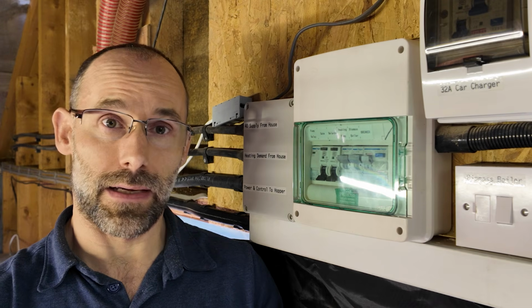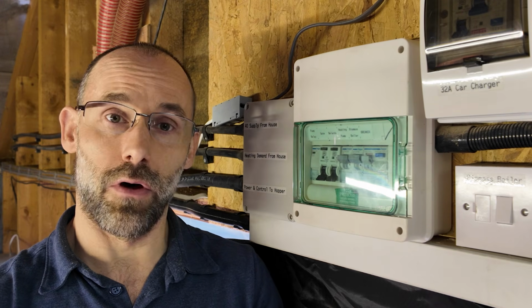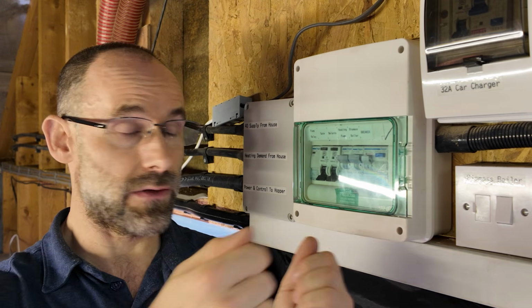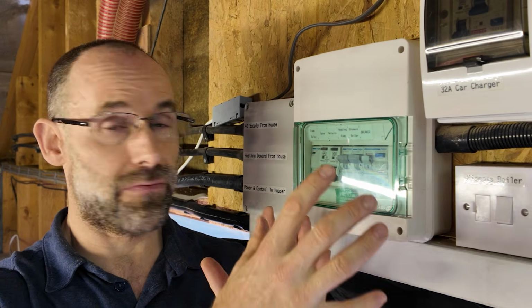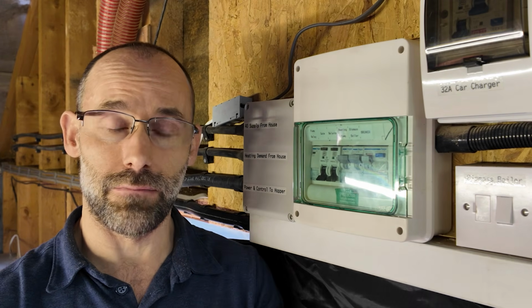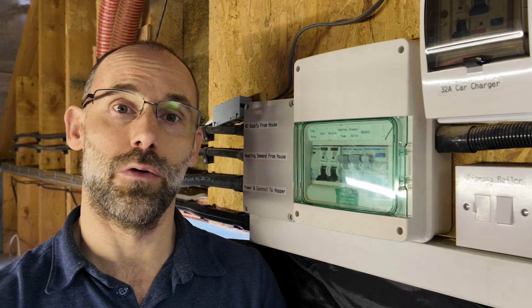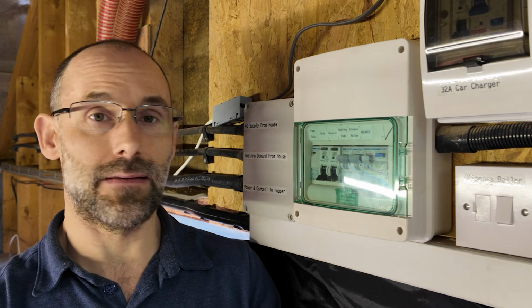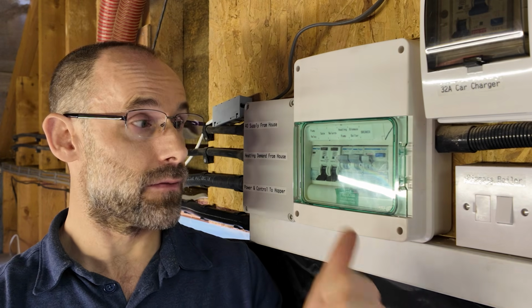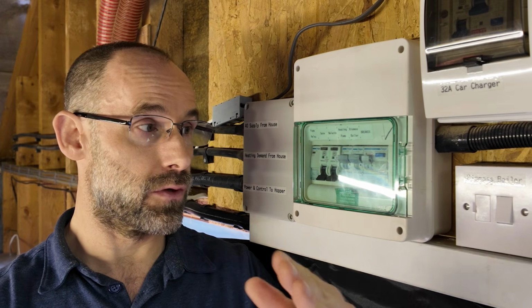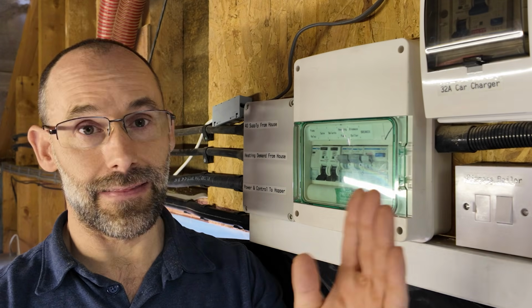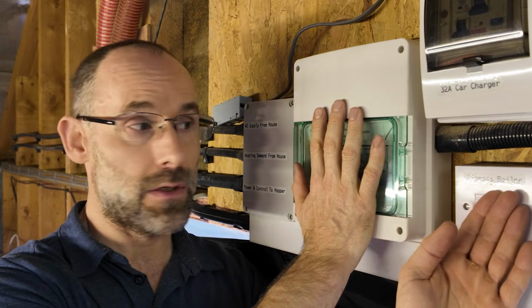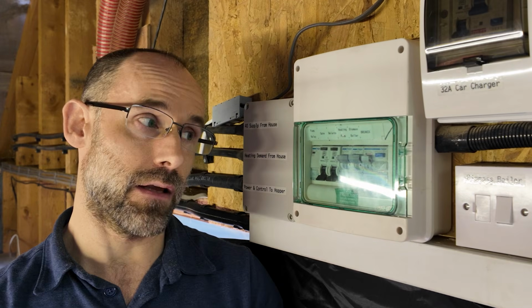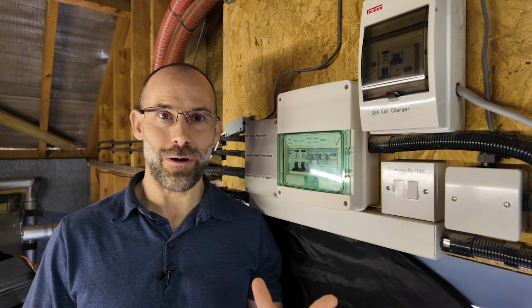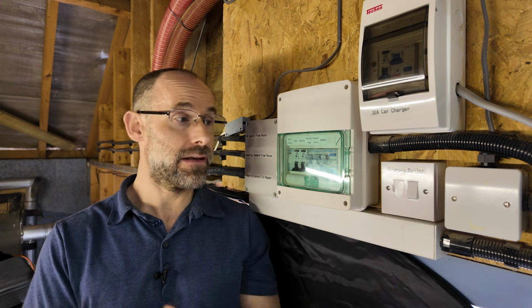In this case, I'm going to do it by calculation, but it can be measured on the multifunction testers, and in circumstances where it's easy and safe to measure that, and where there's sufficiently low noise on the circuit that you can get a reading, that's what you would do if you were really trying to do things properly. So that is ZS, and that is, again, to make sure that your protective devices are actually going to work once you've added in the extra resistance between the consumer unit and the thing that's hanging off the end of it, like this FCU.